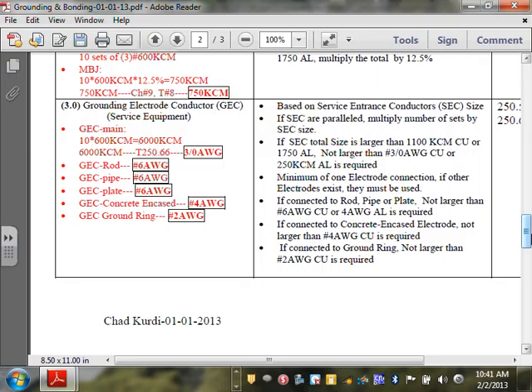The ground ring does not have to be more than number 2. But if your ground ring, like Michelle did for Boston Scientific, is 500 kcm around the building, then the wire from the ground ring into the ground bar has to be 500 kcm because they have to match. So do you guys see this one as kind of the maximum? Because I imagine all these are like roots for the grounding electrode system. You have different roots, and they don't have to be higher than that.